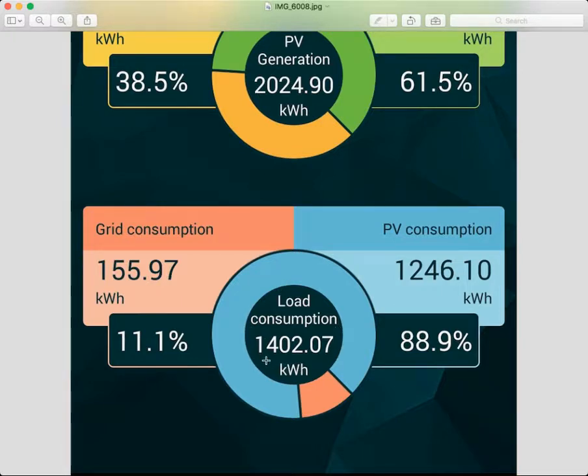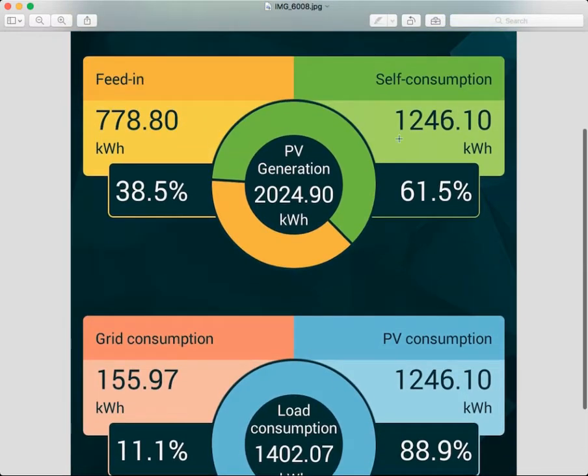The total load consumption is 1,402 kilowatt-hours since the system was installed. This particular house is nearly 90% efficient — between the solar and the batteries, 88.9% of household consumption has come from the sun and what's stored in the batteries. They've only bought from the grid 11.1%, which is about 155 to 156 kilowatt-hours.